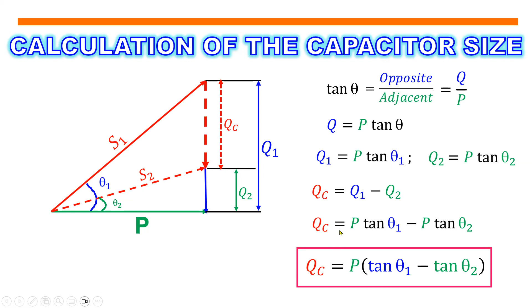So let's have a practice problem. Number 1: a 150 kVA load has a power factor of 0.75 lagging. What size of capacitor in kVAR is required to raise the power factor to 0.91?